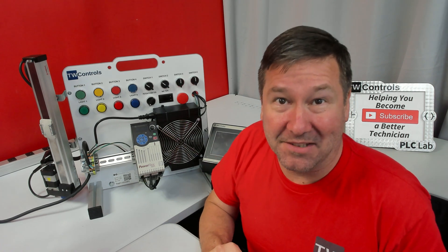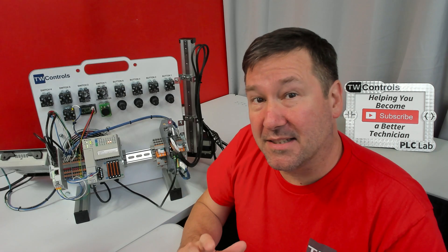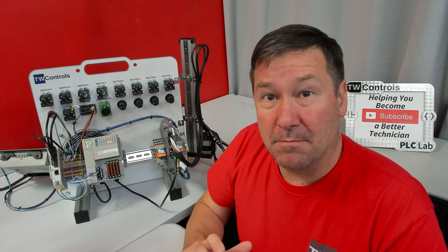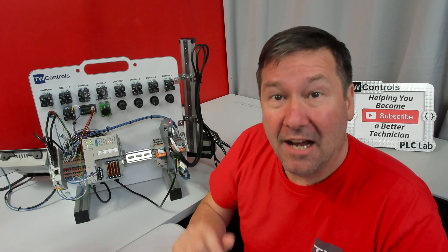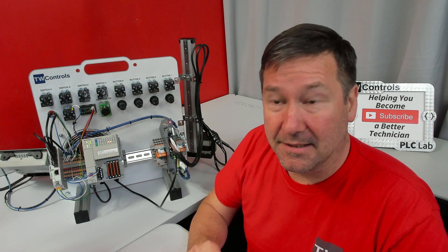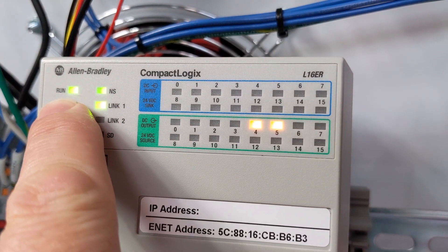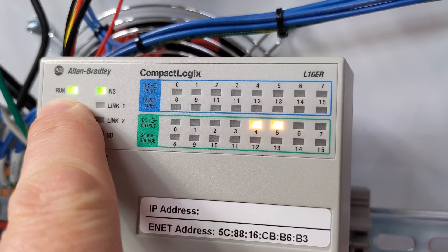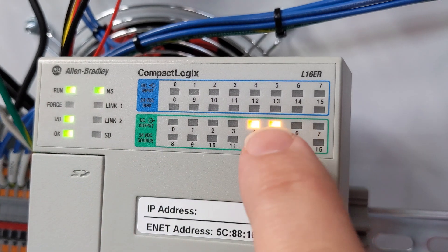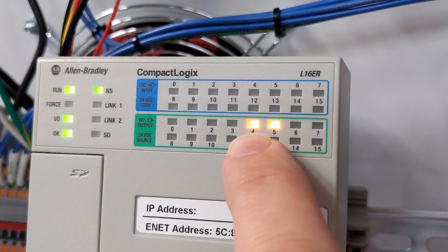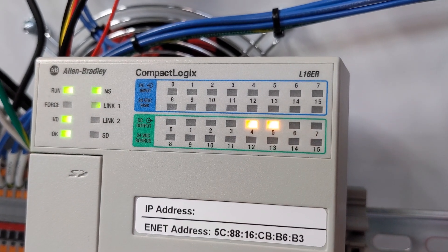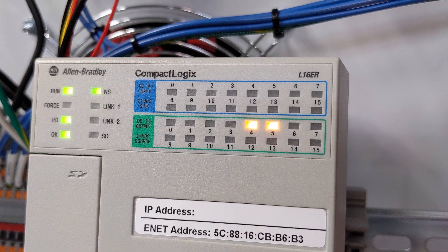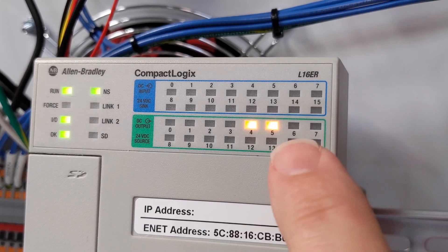Now you're ready to power up your PLC trainer. Your trainer comes pre-installed with the PLC program for your initial testing and your first wiring exercise. First check for the run LED. That tells us our PLC program is running. Then check to make sure output 4 is on. That tells us that we're communicating with the PowerFlex 525 drive.